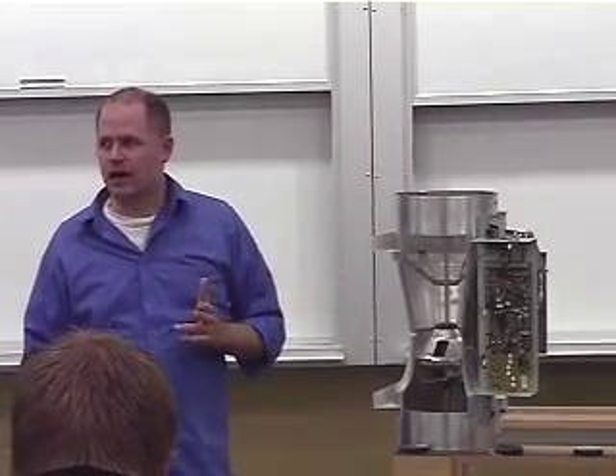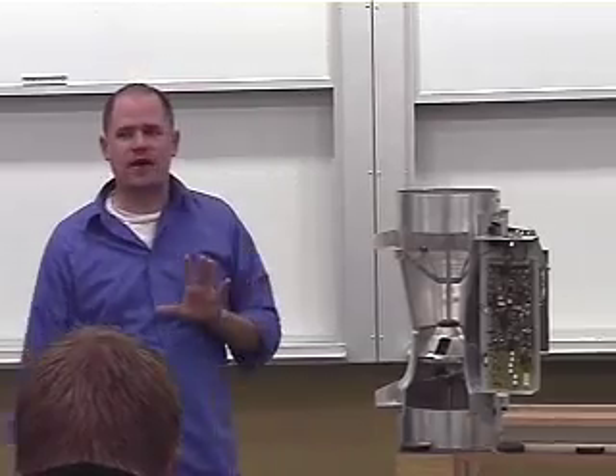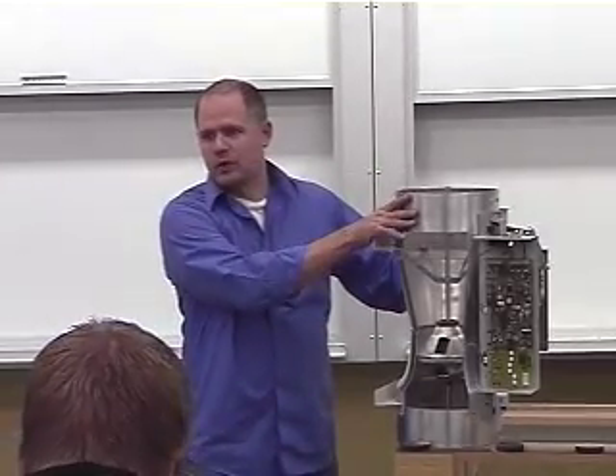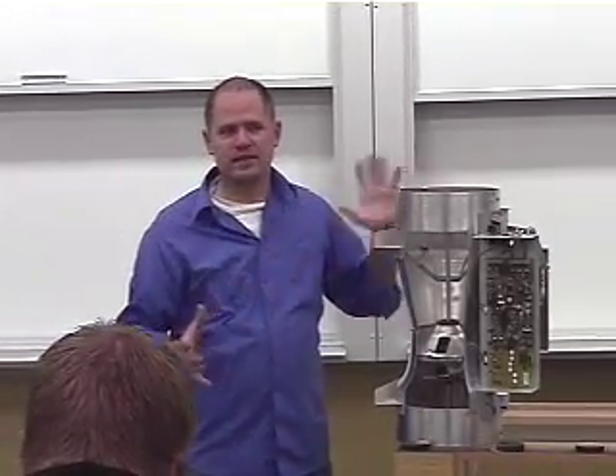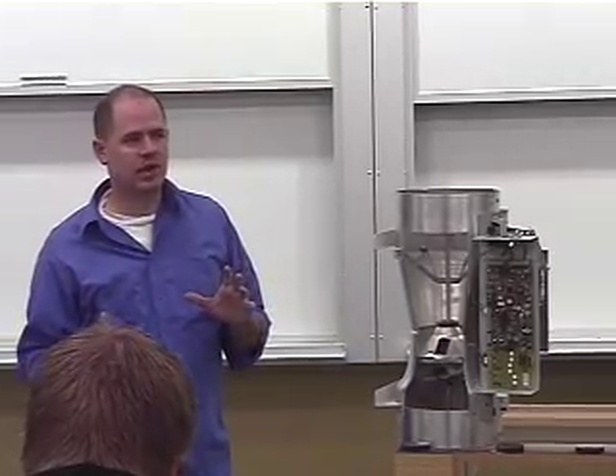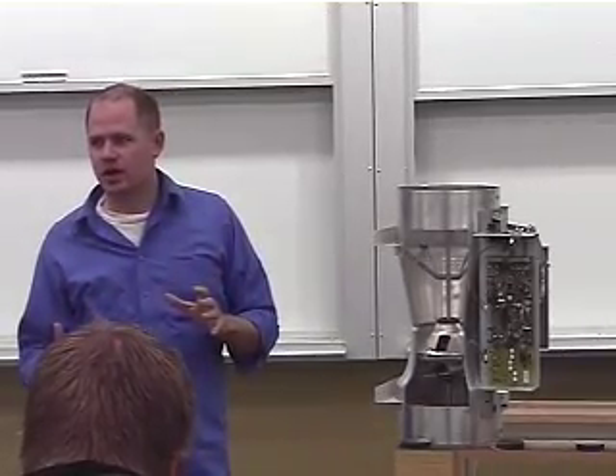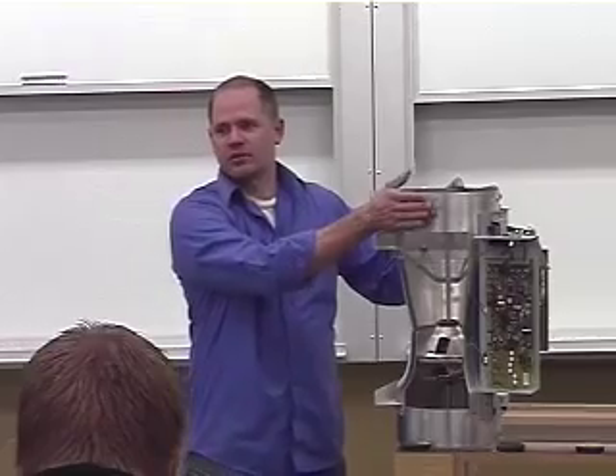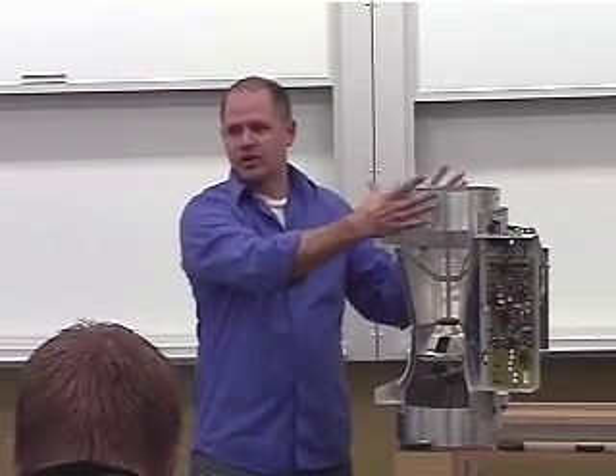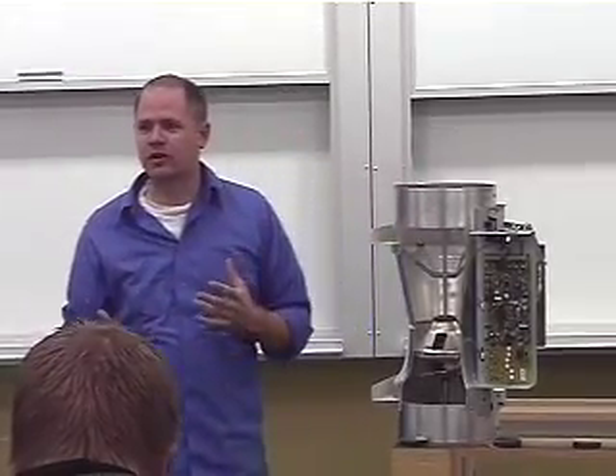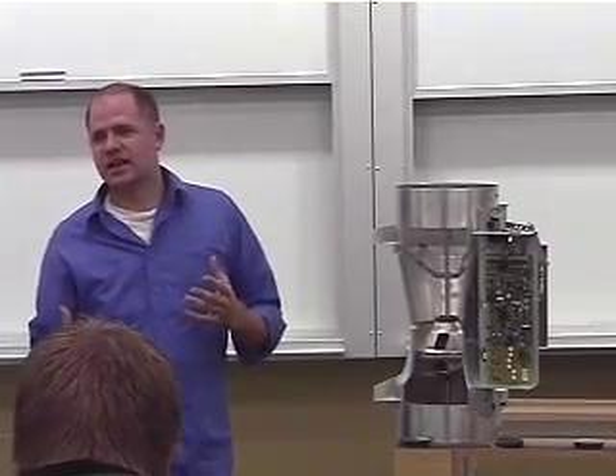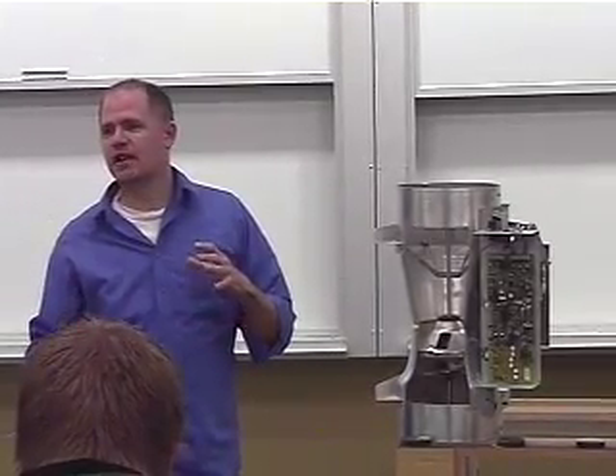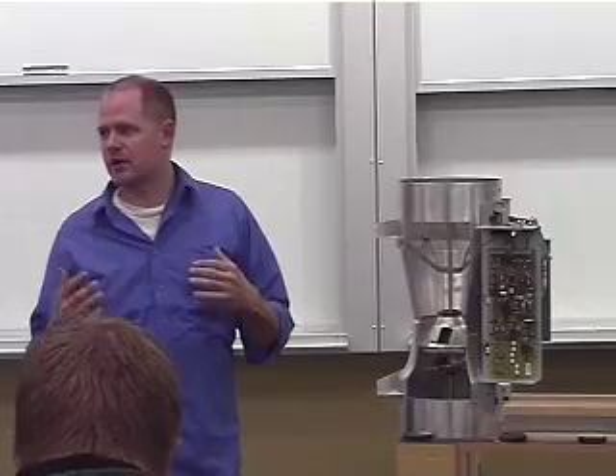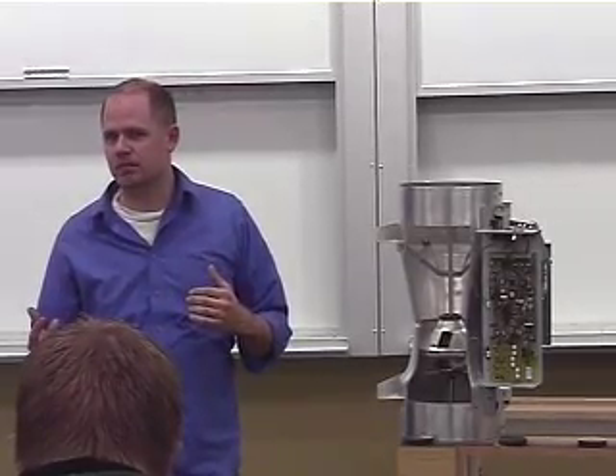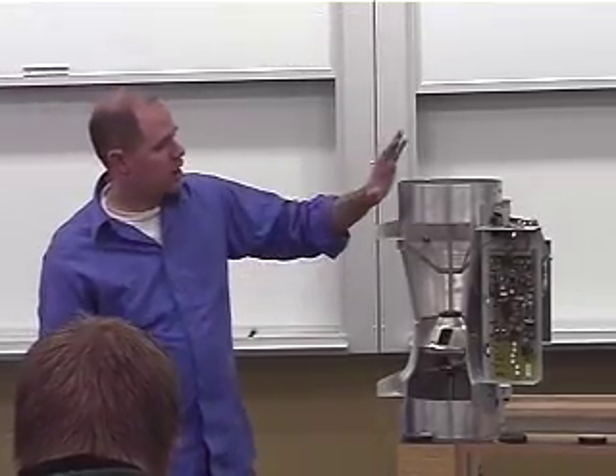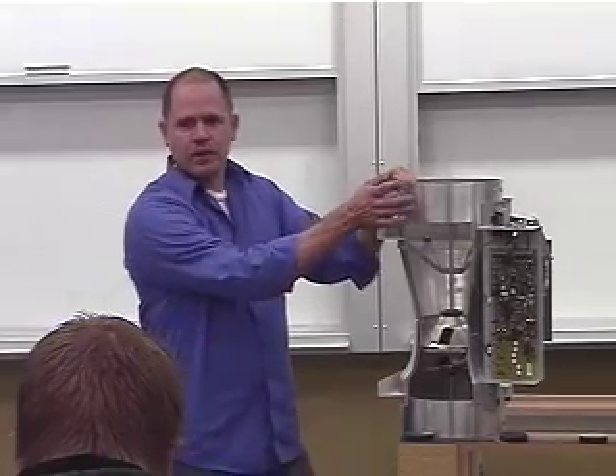One of the other things to be aware of is the type of valve. I only brought in an aluminum one because I don't have a demo one that's a coated valve. But on all of your fume hoods, the valves are actually going to be a brown color. So if you see a brown colored valve, it looks like it's powder coated in brown coating. That's actually a chemically treated valve to resist any corrosion and those kind of things from chemicals that are used in the fume hoods. All of your other valves are going to be aluminum.